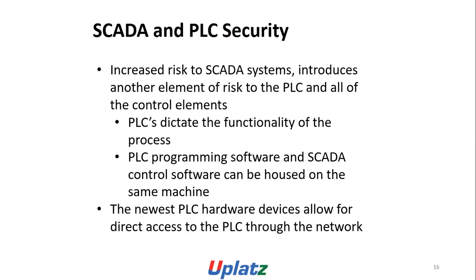SCADA and PLC security: increased risk to SCADA systems introduces another element of risk to the PLC and all of the control elements. PLCs dictate the functionality of the process. PLC programming software and SCADA control software can be housed on the same machine. The newest PLC hardware devices allow for direct access to the PLC through the network.